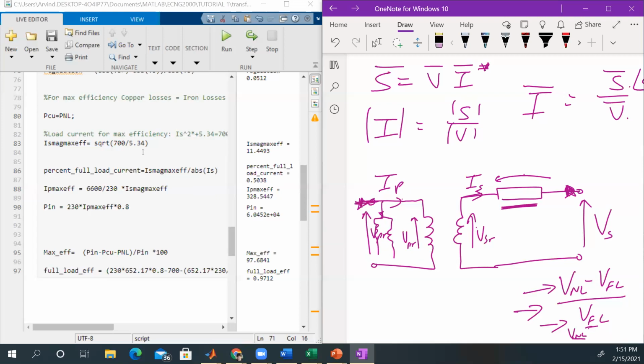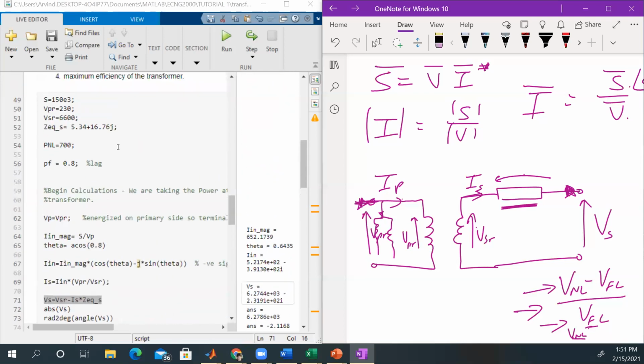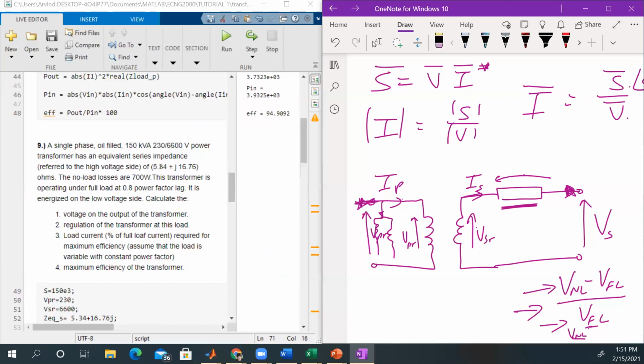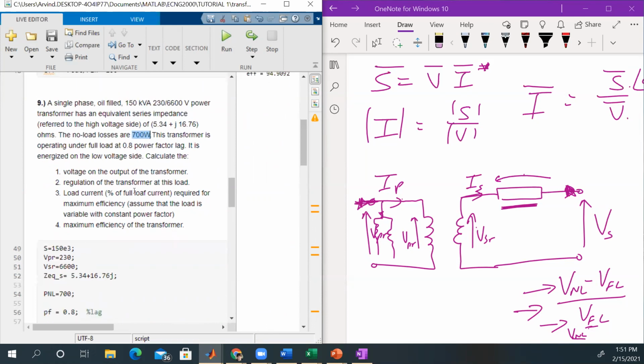resistance, right? That resistance is the equivalent resistance of the high voltage side. We are equating it to the losses in the no load branch, and this is what gives you the maximum efficiency, which occurs when these two losses are the same, right?